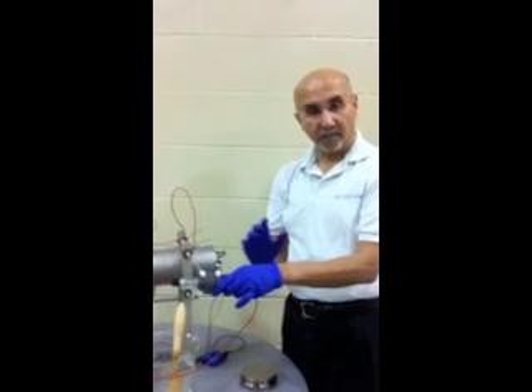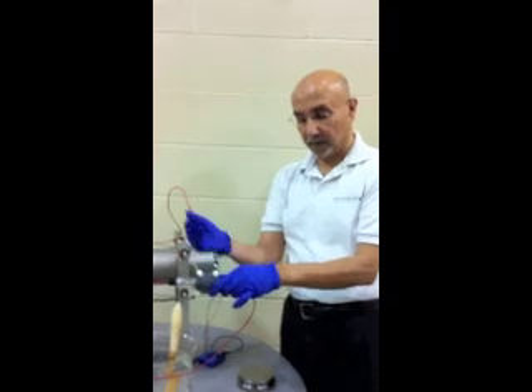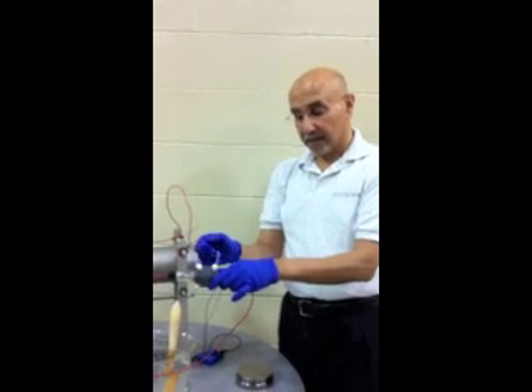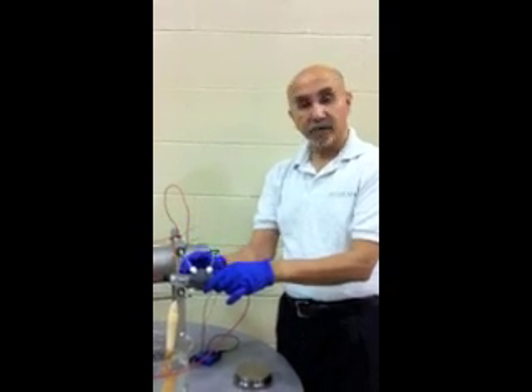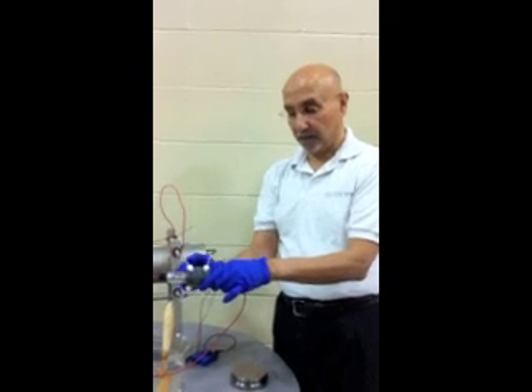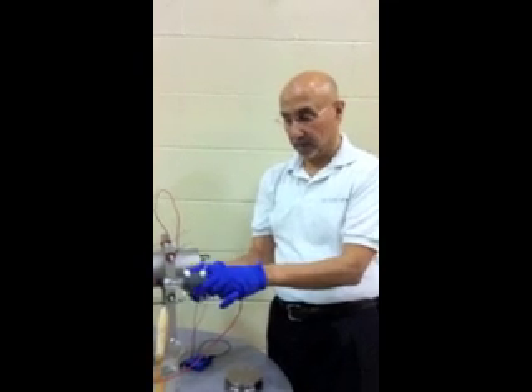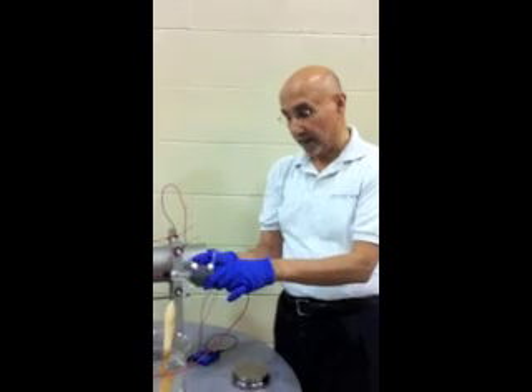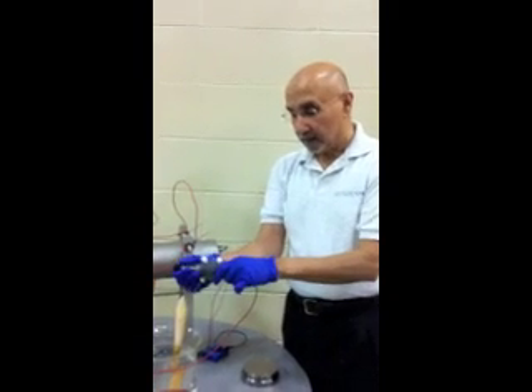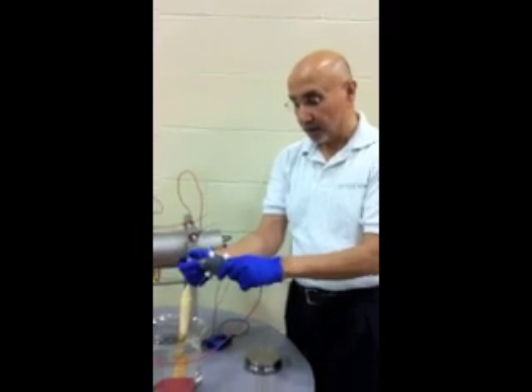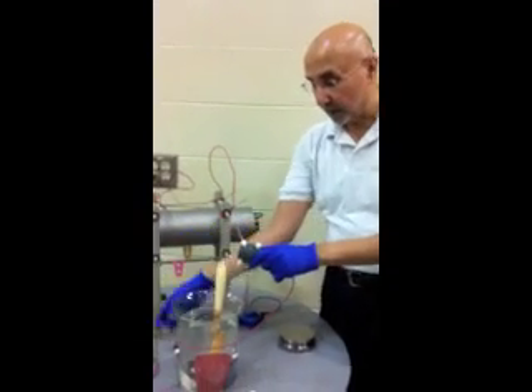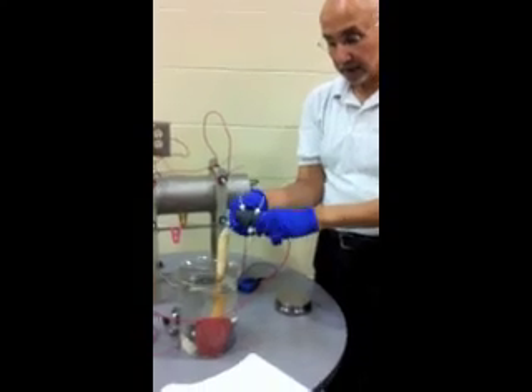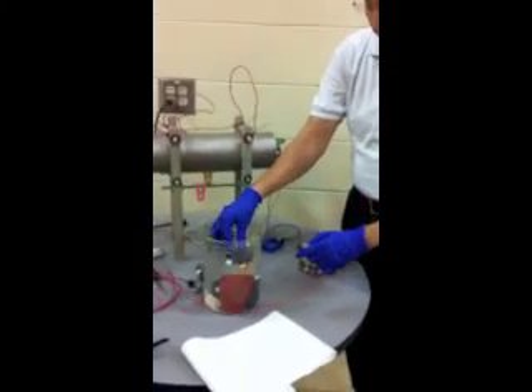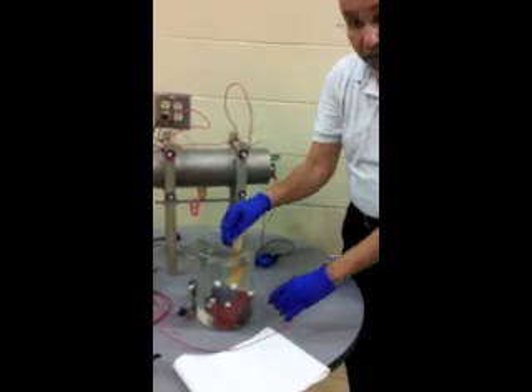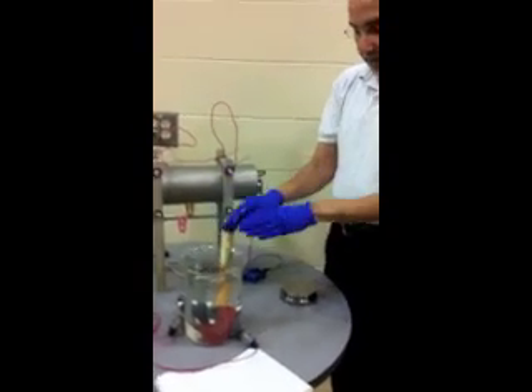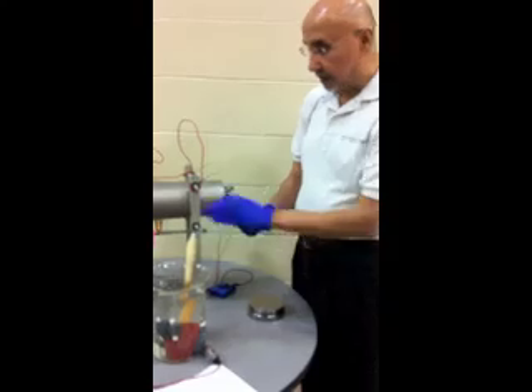This is something we hope to optimize in the months ahead to be able to ensure that more seawater flows in. The sacrifice means that our seawater flows in rather a little slowly, and therefore we need to allow enough time for equilibration with a new seawater environment. In any event, normally this sensor is stored under seawater because the space between the membranes also has seawater at this point. And so it's always stored under a seawater environment. That's as far as the description of the sensor itself.